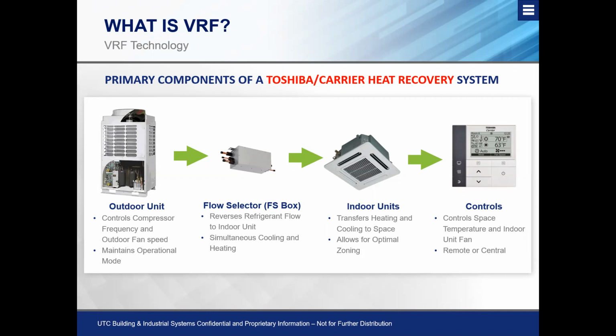So it's a little bit confusing when we talk about 2-pipe versus 3-pipe, what that all actually means. The best rule of thumb that I can give you would be, if you're talking about the Toshiba carrier system, you need to designate whether it's a Toshiba carrier heat pump or a Toshiba carrier heat recovery, which is going to dictate how many pipes you have. And then, if you're dealing with a carrier product, it's going to stay the same whether you have a heat pump or heat recovery, in terms of 2 pipes from the outdoor feeding into the building.